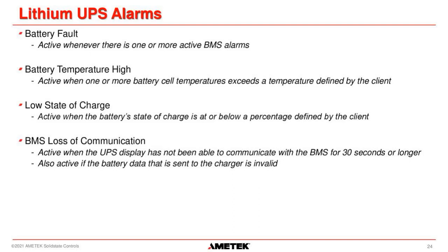And then we also have a BMS loss of communications alarm that will activate when the UPS has not communicated with the battery for 30 seconds or longer. It also will activate if the data sent to the charger inside the UPS is not correct. So if the charger has a problem with any of the data, we will get an alarm.